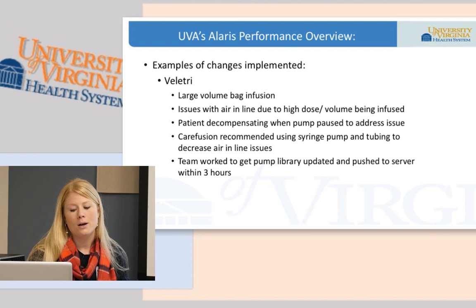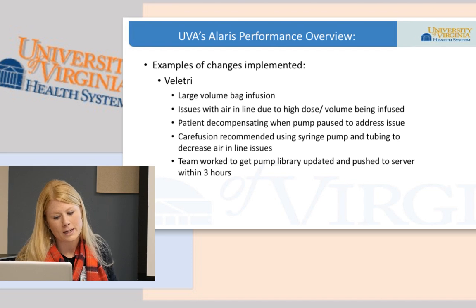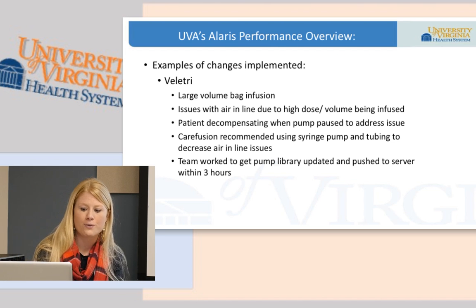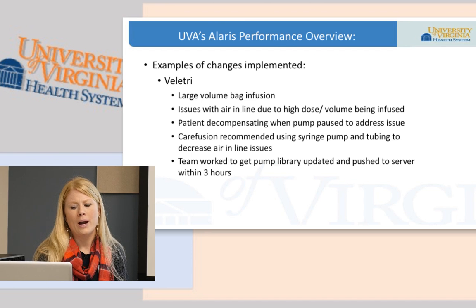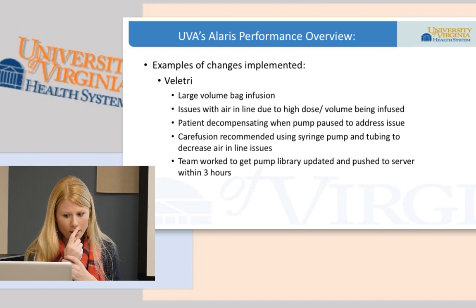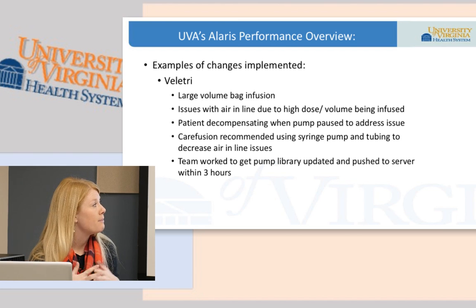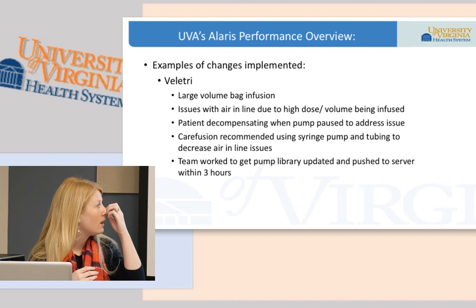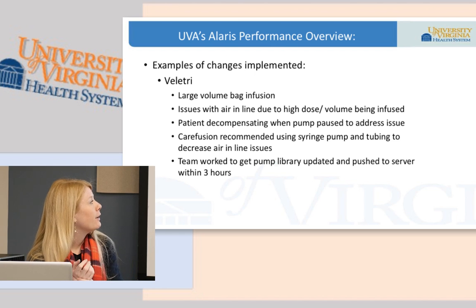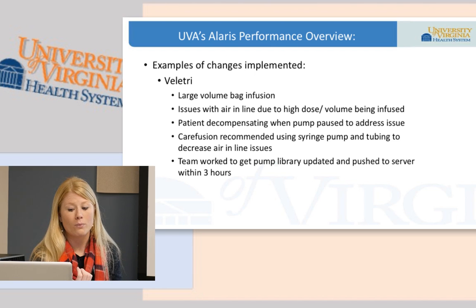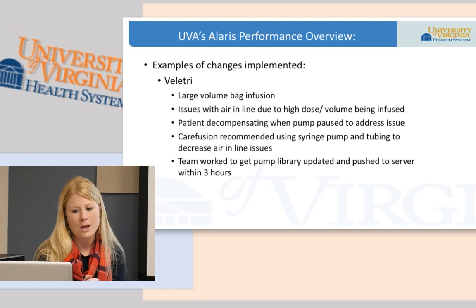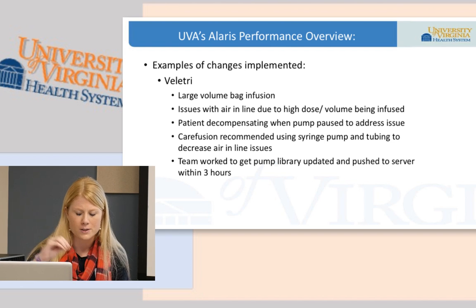Another example of a change that we've implemented: recently there was a patient who was on Veletri receiving the standard large volume bag infusion. They were having a lot of issues with air in the line due to the higher dose and the higher volume being infused, and the patient was having significant decompensation when the pump was paused to address the issue. So this was obviously a big safety concern. An interdisciplinary group worked with CareFusion to figure out what they could do to help this patient, and they recommended using the syringe pump and the tubing, which would decrease the air in the line issue because of the smaller volume.